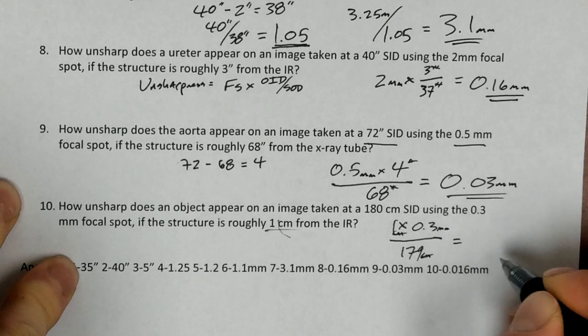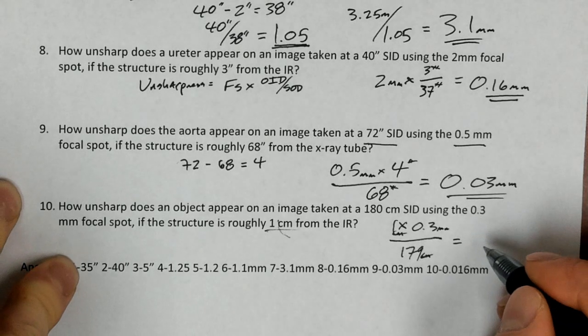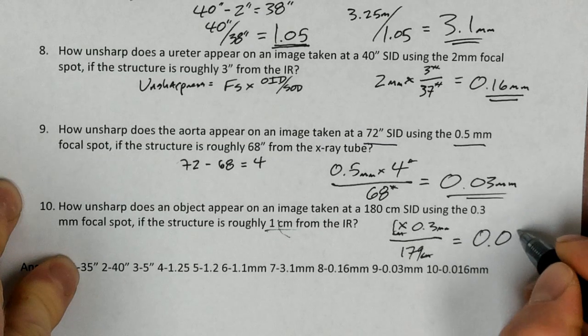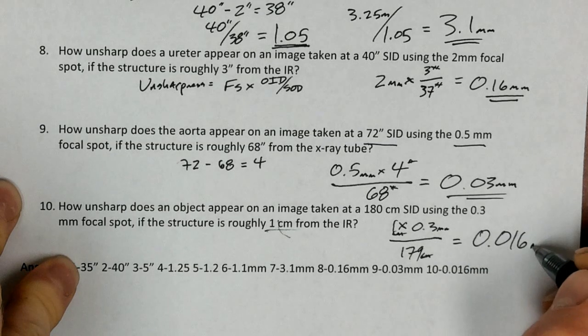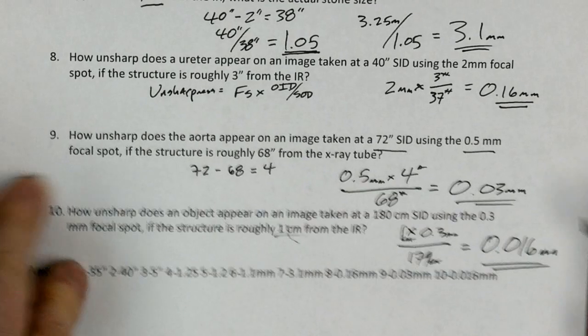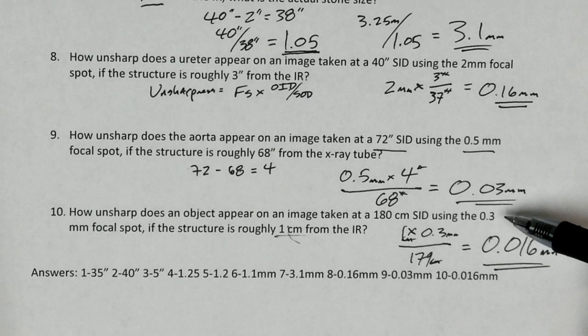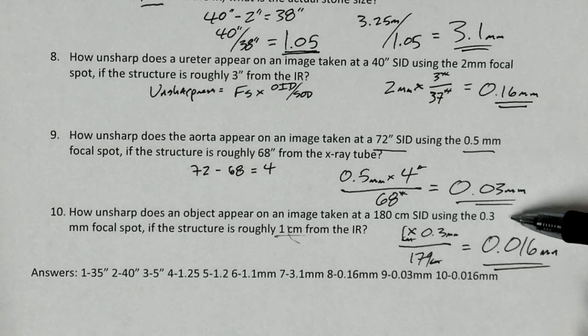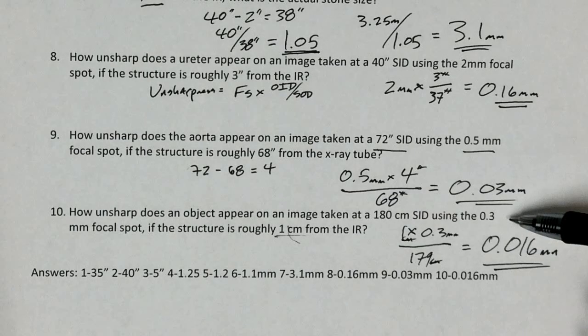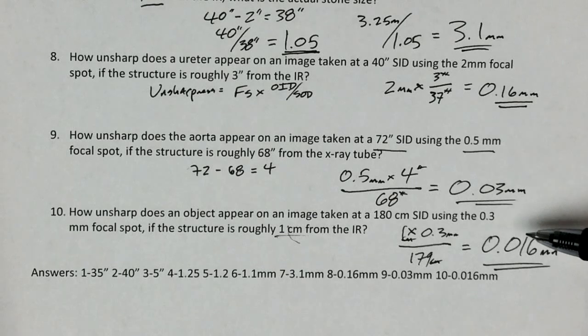All we're left with is millimeters. And when we work this all out, we're going to get 0.016 millimeters. So again, even less unsharpness, so better sharpness, using a much smaller focal spot size, so something that's generally used in, like, cardio cath and stuff like that. Most of our x-ray tubes don't actually have focal spot sizes this small. But hopefully this is helpful.